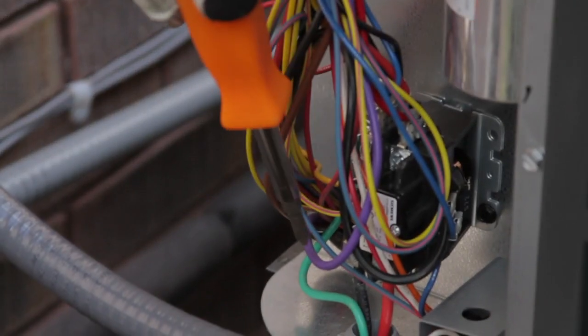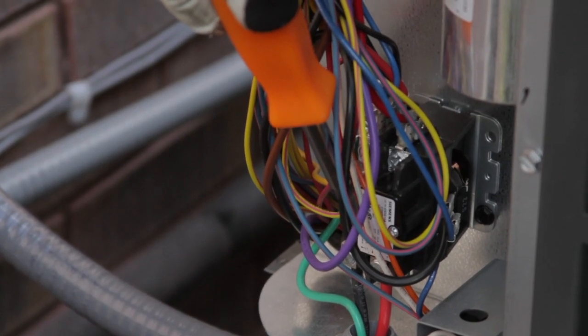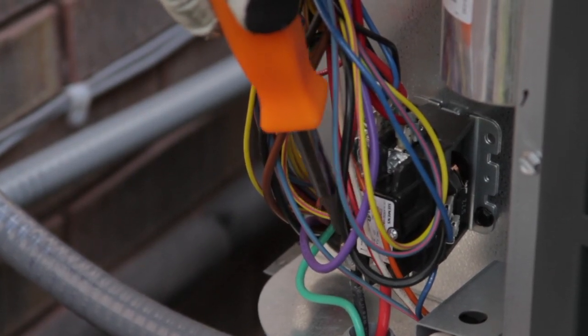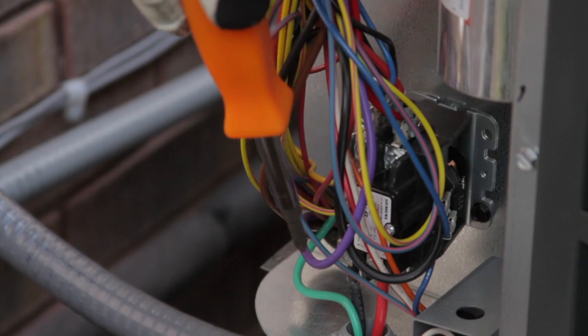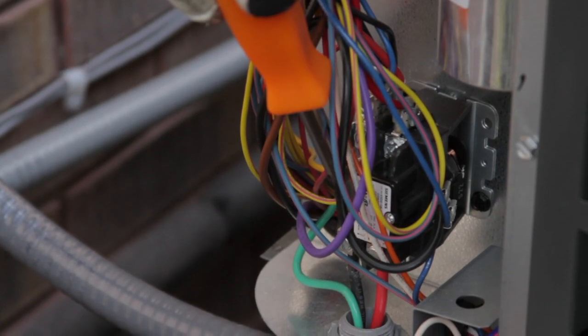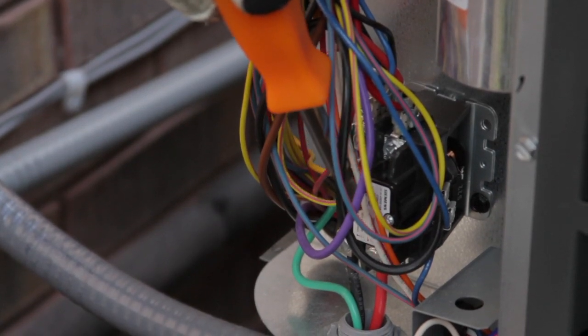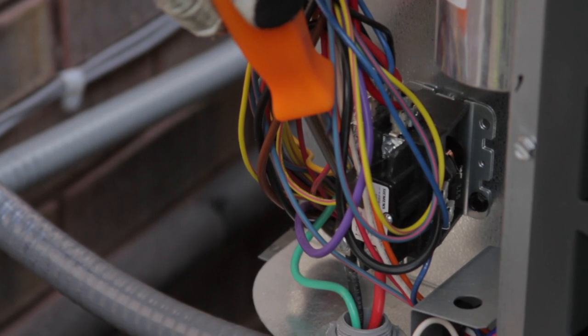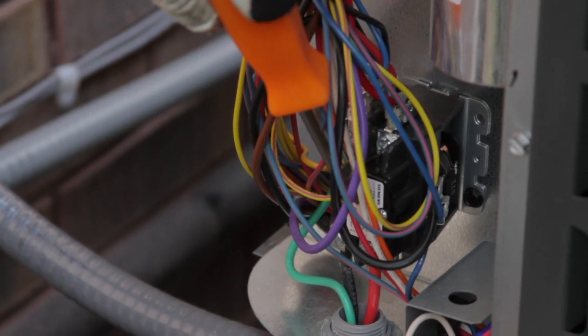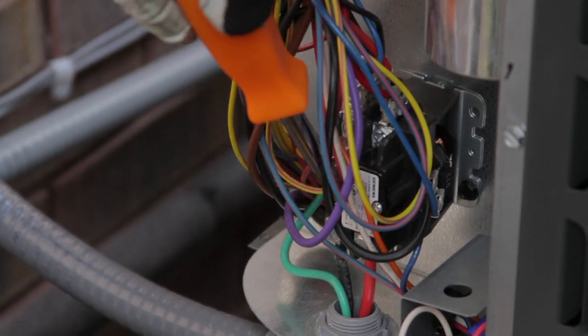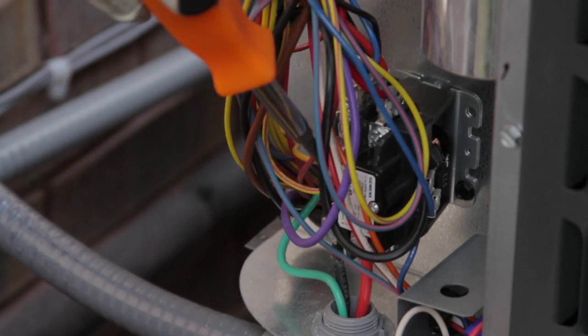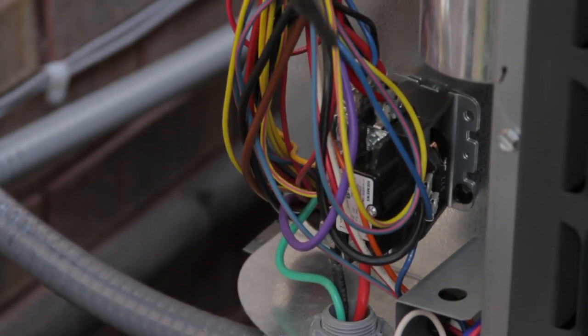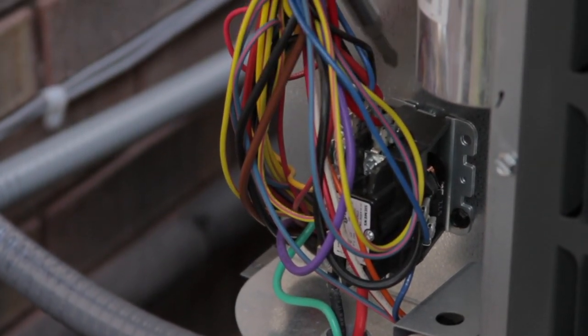This is a contactor. The most common problem that we come across with the contactor is pitting. After so many times of this air conditioner coming on and off, the juice that's going through the inside of here does generate up to like 1,500 degrees, which will cause pitting to the little contactors on the inside, prohibiting the exact amount of electricity going between the two of them.